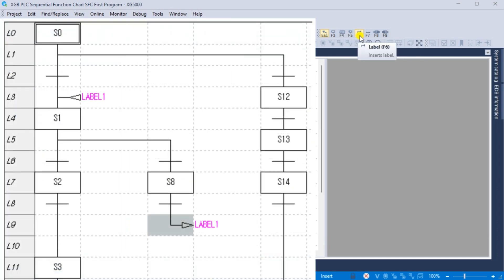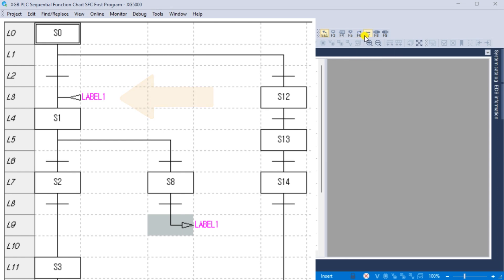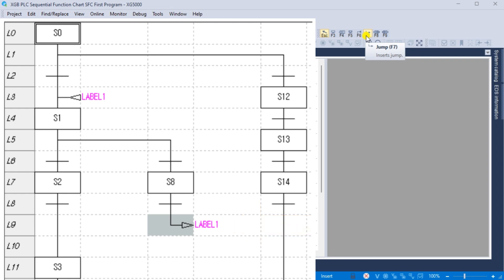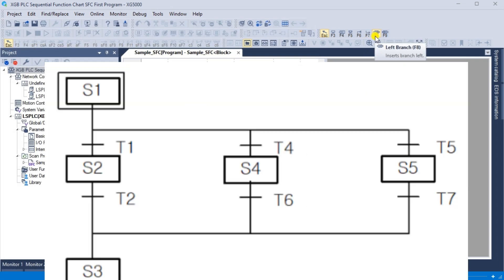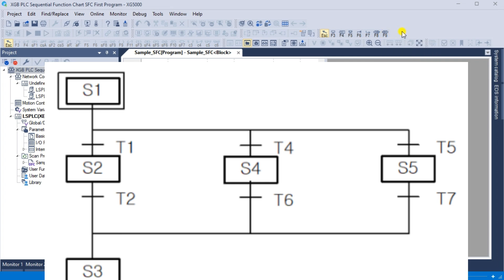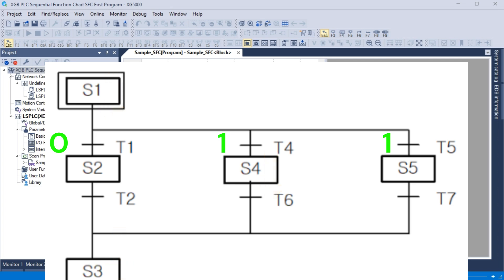Label F6: labels can be placed on your sequential function chart depending on the sequence of operation for your logic. Jump F7: the jump SFC instruction can return to a label within the sequence. Left branch F8, right branch F9: when the upper step is activated, the next transition with a condition set to 1 is activated among the multiple connected transitions. The executed branch is the first transition activated, reading from left to right. For example, if the transition condition of T4 and T5 is 1, the scan order is S1, S4, S3 — the processor chooses the leftmost path.